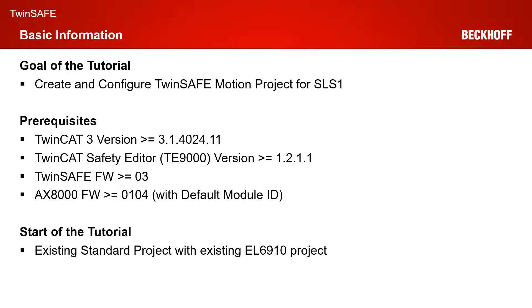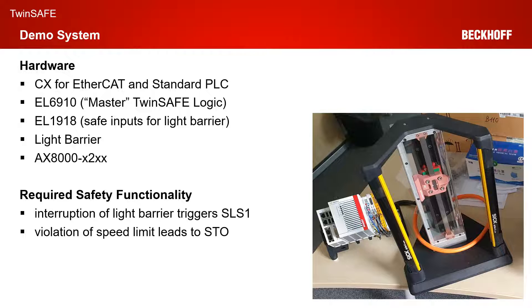Looking at our demo system shown in the picture on the right, we have a CX for the EtherCAT communication and the standard PLC task. We have an EL6910 as the master TwinSafe logic. At the end of the tutorial, we want our AX8000 communicating with this EL6910 as master TwinSafe logic. We have an EL1918 for the safety inputs within our system, with a light barrier connected to the EL1918. And of course, we have an AX8000 X2XX in the safe motion version.